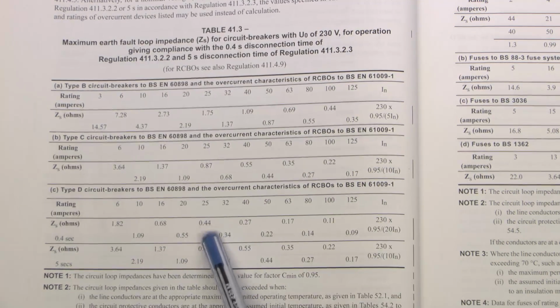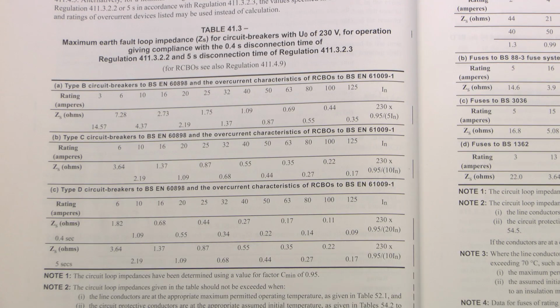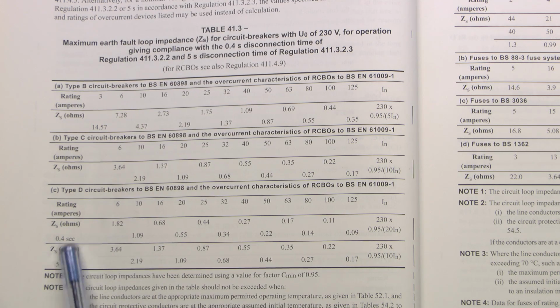So it can actually be quite difficult to meet these things. So in many cases, it's not actually possible to fit a type D at all. Now this table also has an additional line here, which is also for the type D, which is for a 5-second disconnection time.